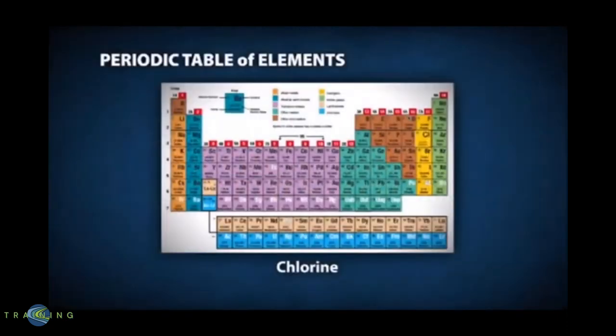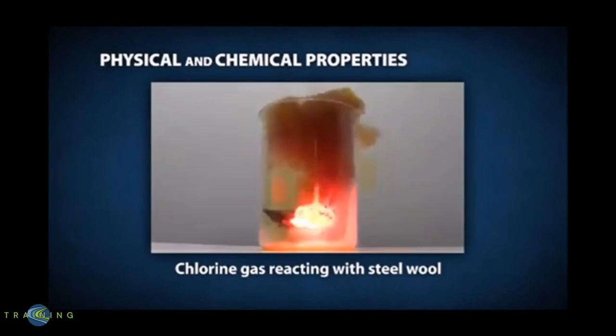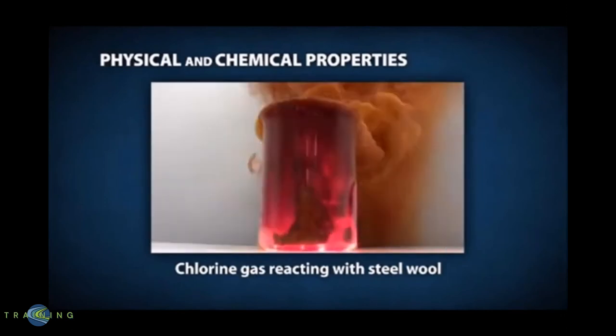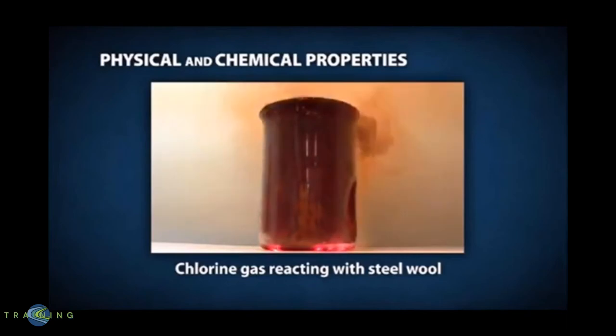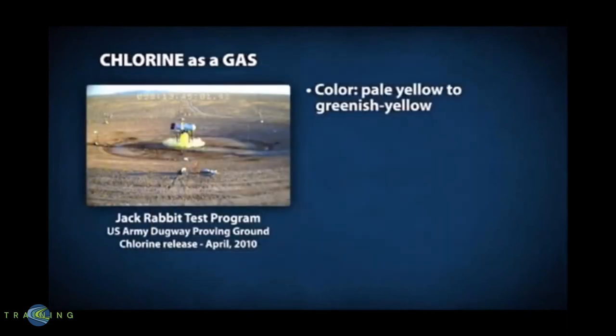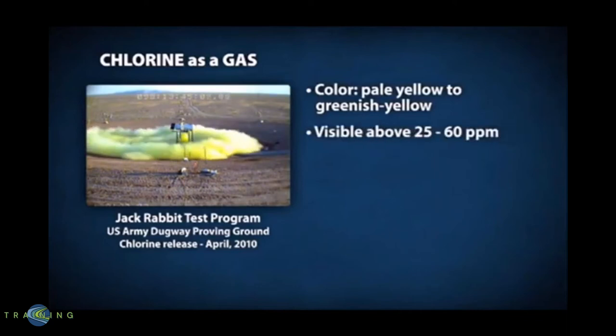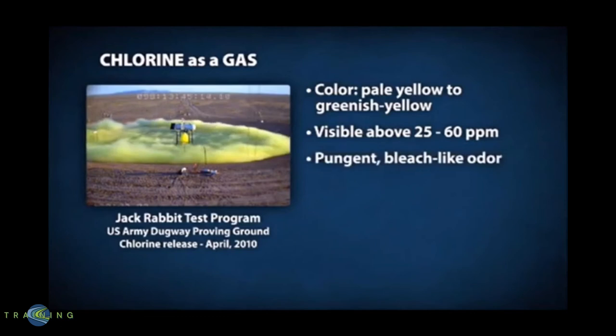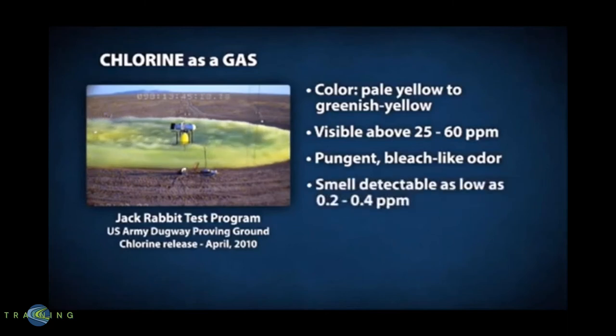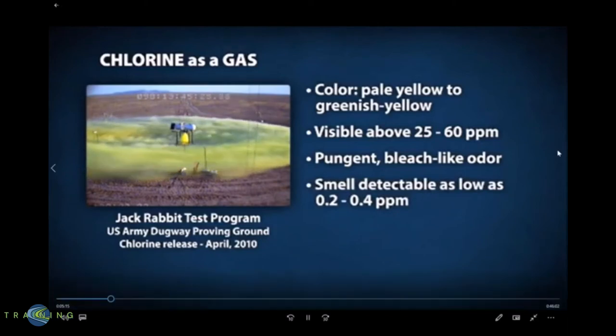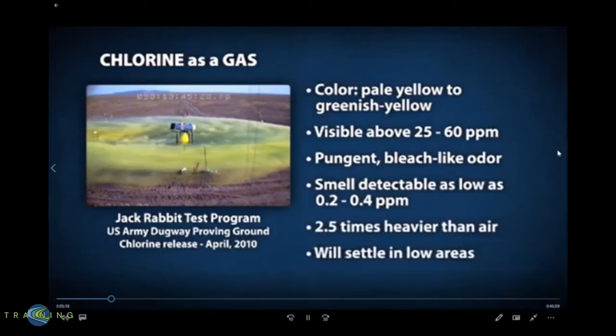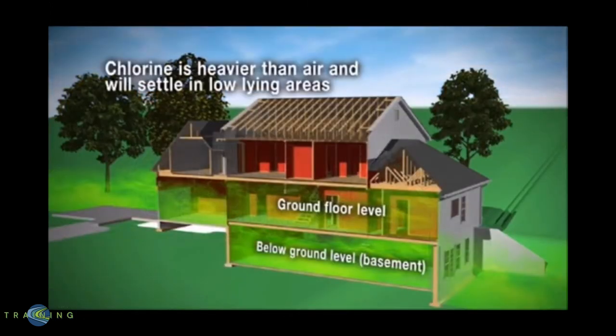Chlorine is identified by the chemical symbol Cl. While it is not explosive or flammable as a liquid or gas, it can react violently with many substances. As a gas, chlorine has a pale yellow to greenish yellow color depending on concentration. It is visible at concentrations above 25 to 60 parts per million depending on humidity. It has an extremely disagreeable and pungent odor, similar to chlorine-based laundry bleach, and is detectable by smell at concentrations as low as 0.2 to 0.4 parts per million. It is about 2.5 times heavier than air, so if released, it will accumulate at floor level and below ground level.